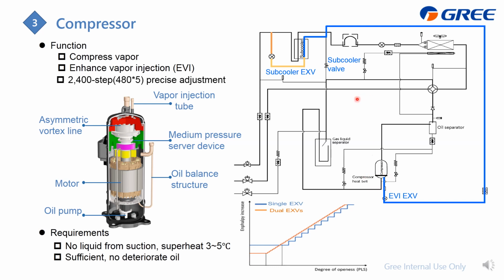And here is a question: during EVI, is this subcooler valve on or off? The answer is it should be off, because we need to conduct the refrigerant, which is this part, to the compressor. If you make it on, you can find that it connects to this part, which is the low pressure, and the refrigerant will always go to the low pressure, not the medium pressure, which is for the EVI injection.